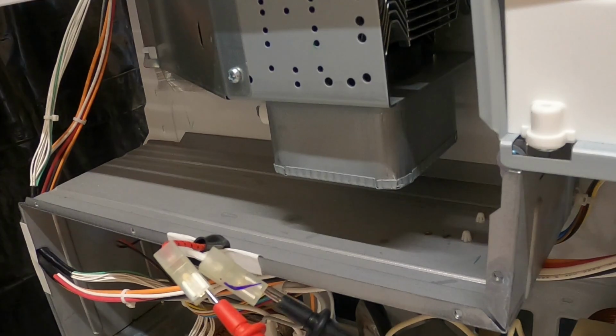So at this point, you've eliminated everything else. You know you've got power into the transformer. You know you're not getting any loud hums from a shorted diode. You can check for an open diode, but you have to have a really, really heavy-duty meter that uses a 9-volt battery. And in my whole career, I've seen one open diode. You know it's not the capacitor. And again, in my career, I've seen one open capacitor. You can also check for that. When I say open, I mean there's no electrical path through the component.